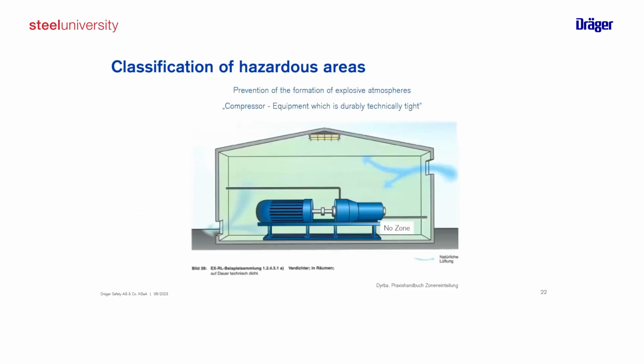Here's an example from a handbook to give guidance on how to design applications, and by using different measures of primary explosion protection, what is the resulting zone in this application. This is a compressor stage, which is designed durable, technically tight. So we expect under normal operation, it will not leak. So all connections are tight.